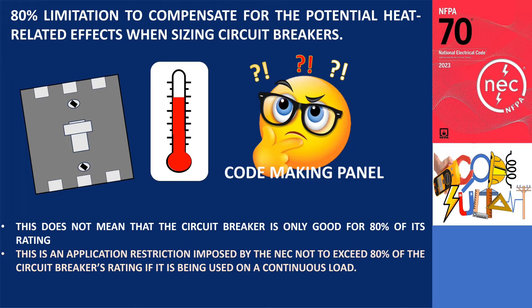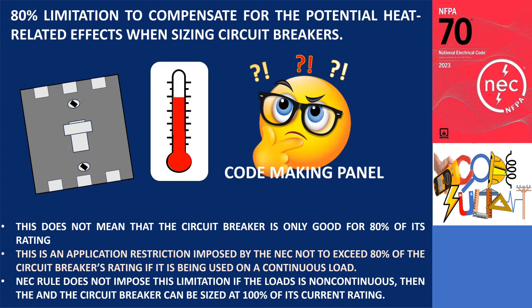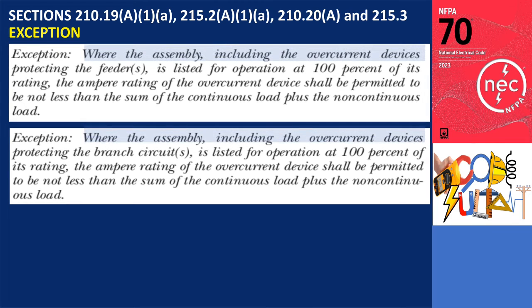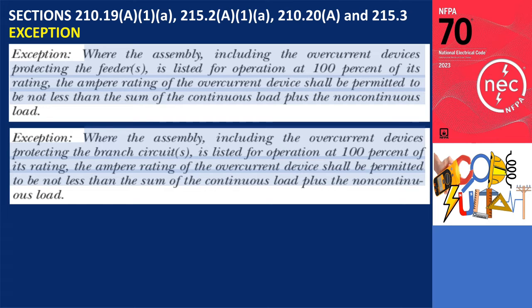In cases where circuit breakers solely supply non-continuous loads, the NEC rule does not impose this limitation, allowing the circuit breaker to be sized at 100% of its current rating. Like many rules, exceptions exist within the electrical code. In Sections 210.19A1A, 215.2A1A, 210.20A, and 215.3, there is an exception stating: where the assembly, including the overcurrent device protecting the branch circuit, is listed for operation at 100% of its rating, the ampere rating of the overcurrent device shall be permitted to be not less than the sum of the continuous load plus the non-continuous load.